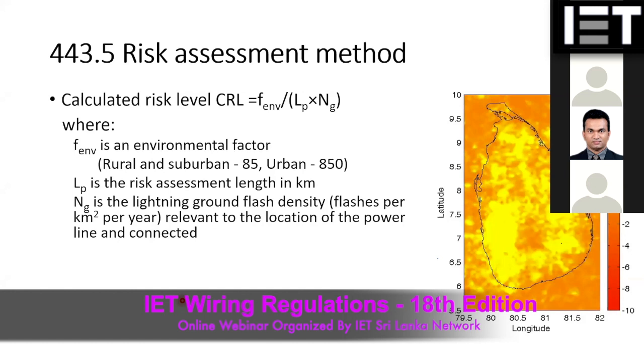When you look at this risk calculation, there is an equation where you have F environment, the environmental factor, divided by LP. LP is the conductor length or the cable length, and NG is the lightning probability in that area, so that the lightning will create the highest risk of overvoltage. Because of that they have adapted this as the risk assessment. It's a very simple equation that anybody can use to find out the risk level of that particular installation.